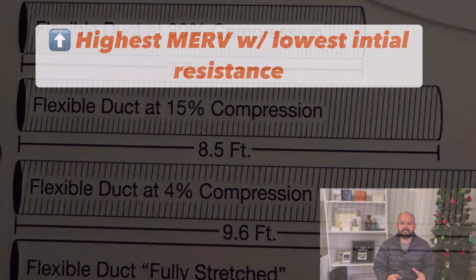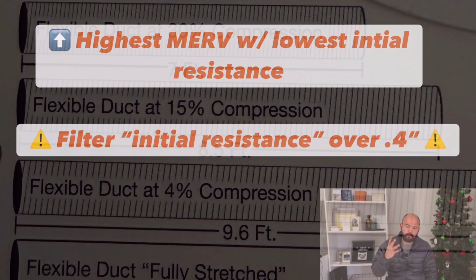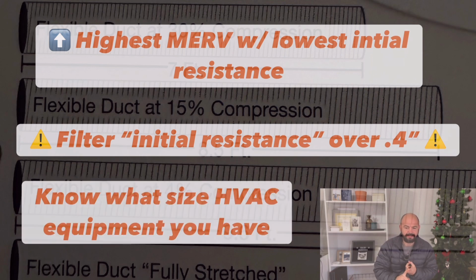Lastly, to simplify all of this: if the filter's over 0.4 inches of initial resistance, you should be very cautious when selecting that filter. Remember, know what size HVAC equipment you have, especially what drive your blower motor is, and you're going to be flirting with danger on a 4 or 5 ton system if the filter is over 0.4 inch initial resistance.